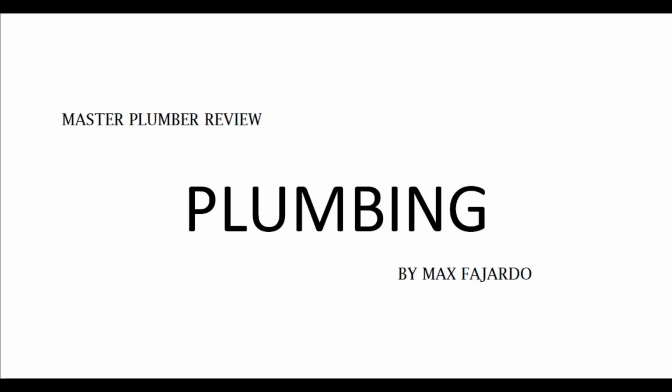The drilling and tapping of house drain, soil pipe, and waste or vent pipe, and the use of saddle hubs or bends are strictly prohibited. B. Dead-end fittings. Dead-end connections in any drainage installation should not be permitted. This portion of the plumbing system will only accumulate waste and sludge. Figure 6-8 shows the dead-end connection.